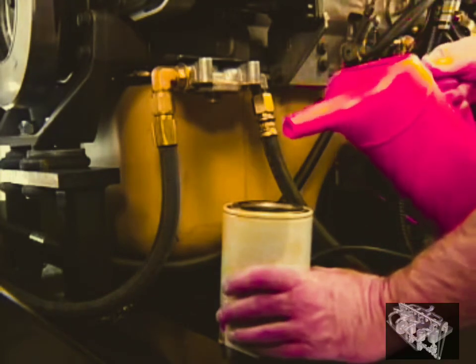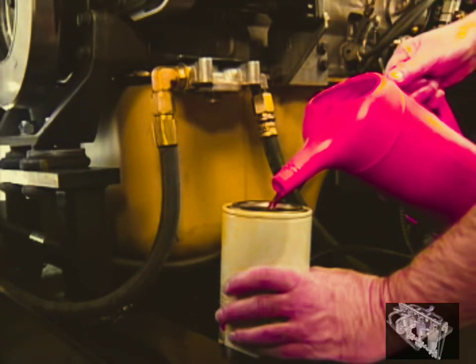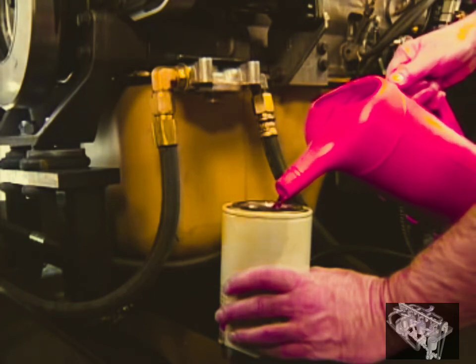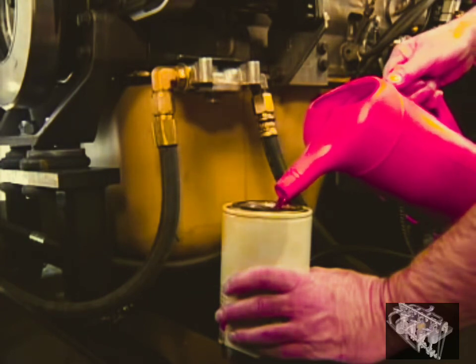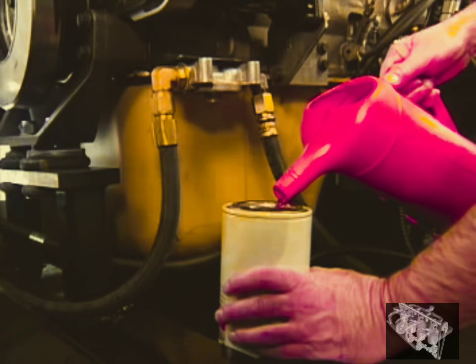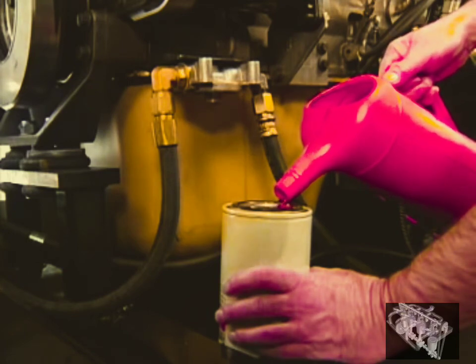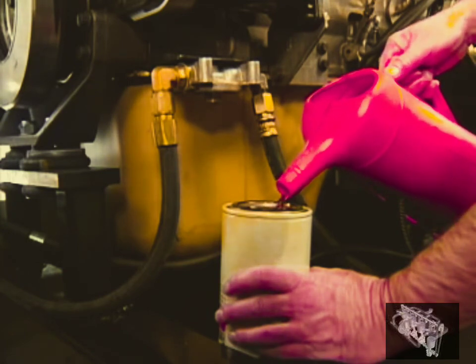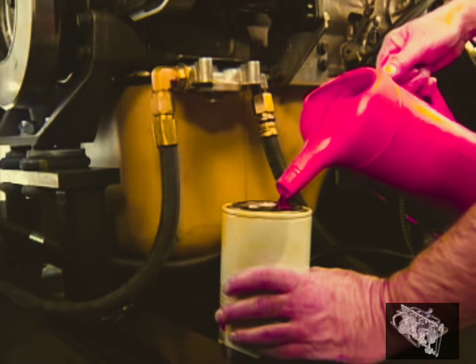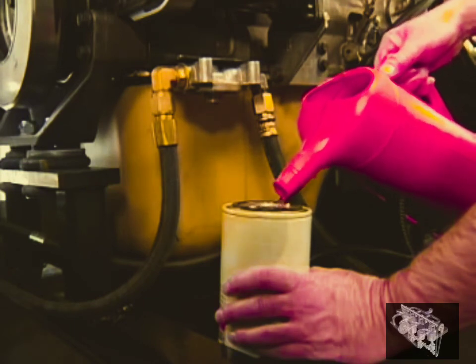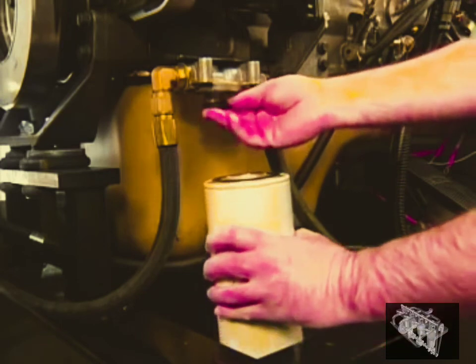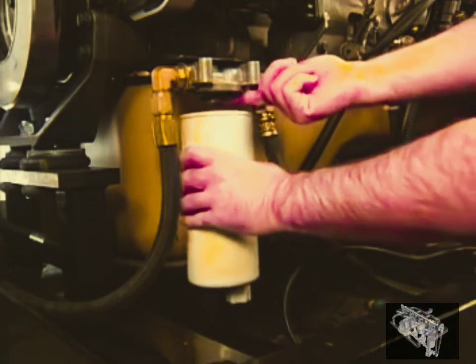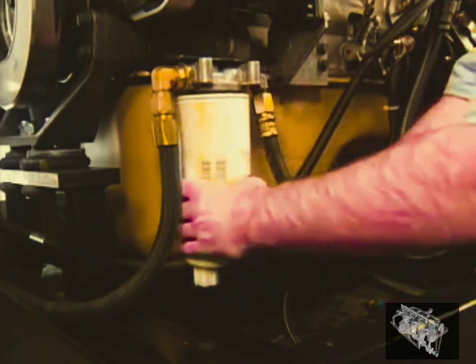Priming a system that has been run out of fuel or has new filters installed may require several lift pump cycles. It is recommended that the OEM-mounted 10-micron suction side filter be installed full of clean diesel fuel and the engine-mounted 2-micron filter be installed empty. It is also important that the 10-micron filter have a standpipe. If the 10-micron filter has a standpipe, the fuel lift pump should be able to fill a dry pressure side system within 3 or 4 lift pump cycles.